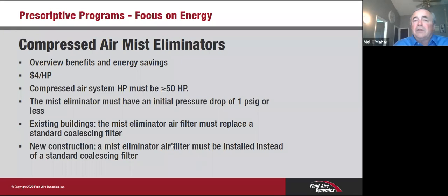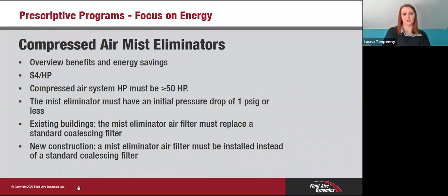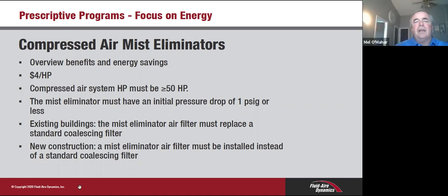So, is there anything you want to add to that, Laura? No, that pretty much covers it. If you lower the pressure drop, you don't have to have your pressure set as high to compensate. And again, that 2 psi for 1% on the compressor is how that's saved. Yeah, that rule of thumb is a big one that opens a lot of ears when I go out into the field, and you probably see that also, Laura.